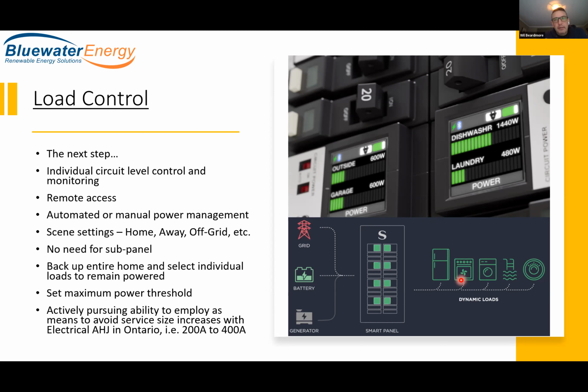The way we're particularly looking at employing this system is for the home I referenced earlier that needs to go to 400 amps. We say, okay, here's all the loads in the home, everything's on a power module, everything's being monitored, and we set the maximum allowable energy consumption at, let's say, 180 amps. Then we prioritize each of the circuits - priority 1, 2, 3. We tell the system if we get to that 180 amp limit, or start approaching it, we begin to limit what is allowed to operate, causing certain things to not energize until something else shuts off.